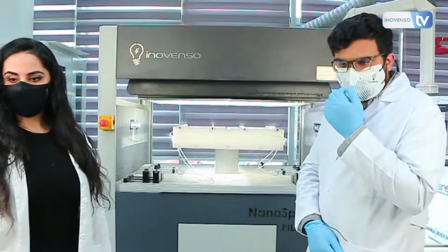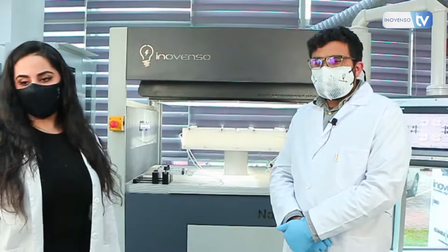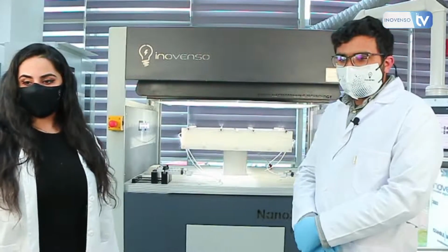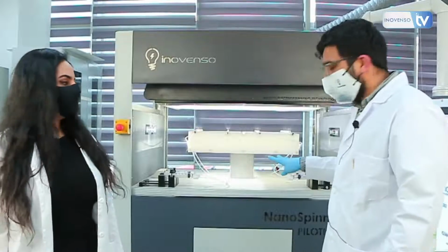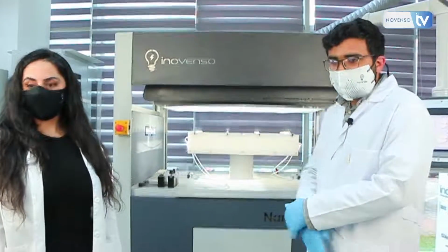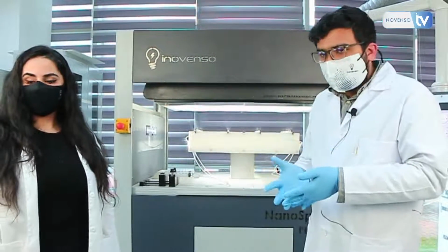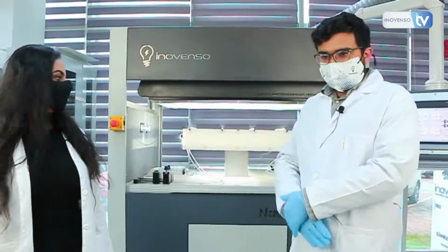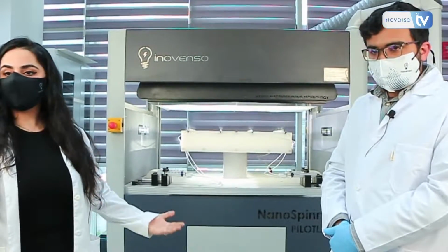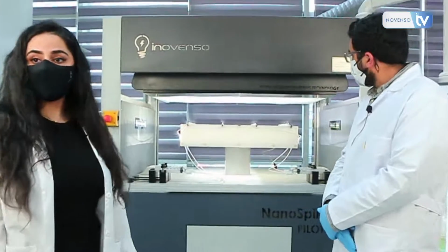Let's address another question. Can water and an organic solvent be used simultaneously in two different syringe pumps? Yeah. Of course, you have 4 different syringe pumps, so you can use 4 different compositions, one for each pump, to create, say, a blend structure or some mixture. You're welcome to do that. Since you have 4 syringe pumps, you can use different solvents while operating the system.